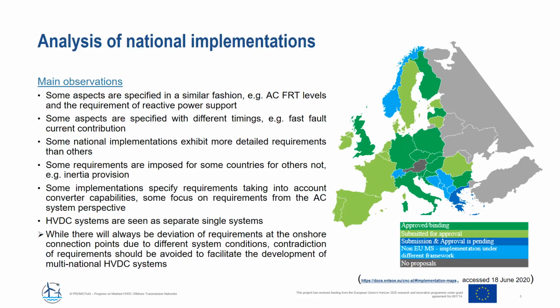So for example, the fast fault current contribution in the different national grid codes. What's also striking is that some national implementations exhibit a lot more detailed requirements than others. So there could be a fast fault current contribution only specified for symmetrical faults. But for example, in the German and Spanish grid code, there are very detailed requirements on how to specify the fault current also under asymmetrical AC faults.